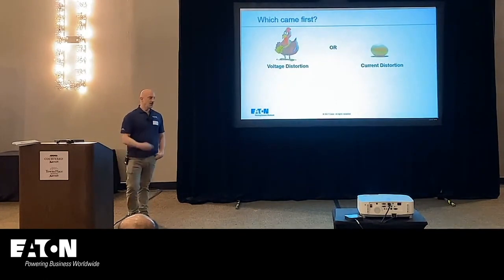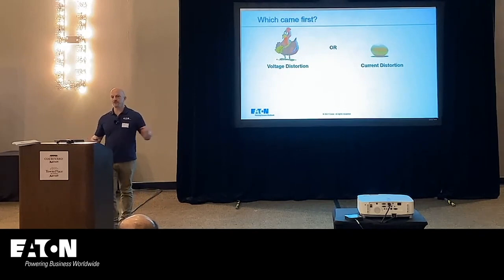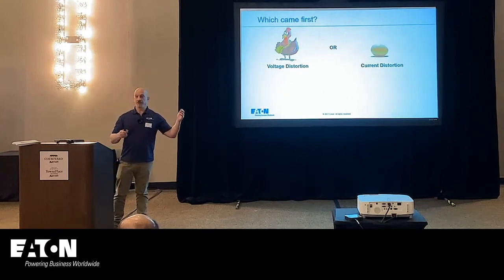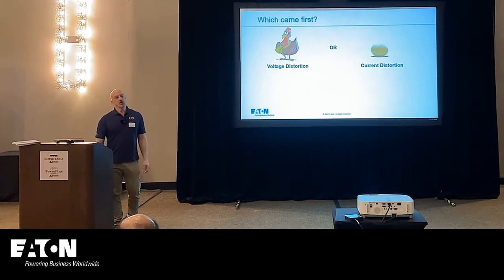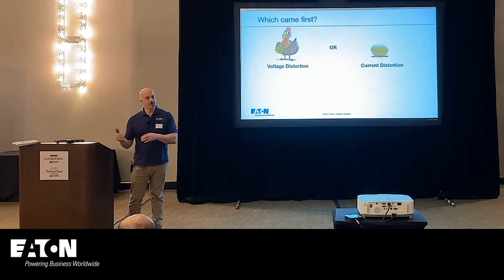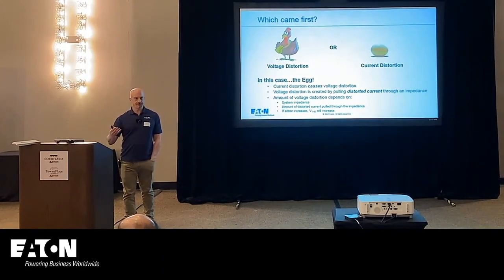So now which came first? Voltage distortion or current distortion? What did we just talk about? What causes what? Does voltage distortion start or current distortion start? Current, right? So this is where that constant current source comes into play. If I have a constant current source and I'm pushing that current through my system, however much current distortion I push through my system is going to dictate how much voltage distortion I have.